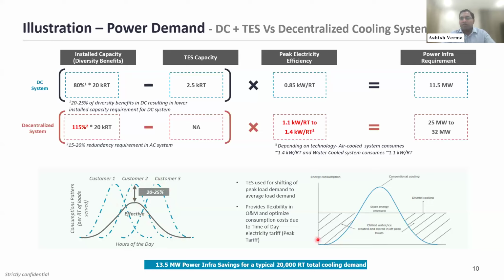And how the thermal energy storage tank works is like, this is the bell curve, which every load pattern follows. So this portion above this horizontal line is the peak, what is needed for the peak time. What district cooling and thermal energy storage system does is, this hatched portion is the time when we charge our thermal energy storage tanks, and we utilize it during this peak requirement. And that's why we are able to meet the cooling demand of the peak time utilizing lower capacity equipment. So this is the benefit we can get with the thermal energy storage system coupled with a district cooling system.